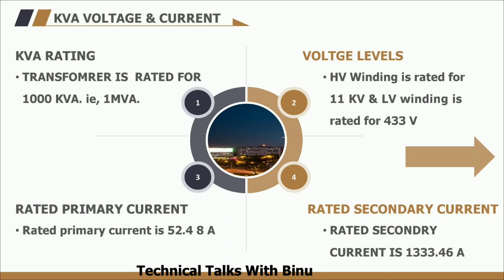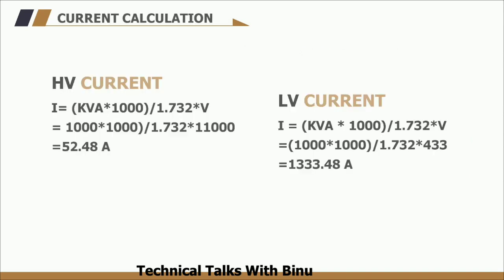Now let's see how this can be calculated. Rated current on the HT side is given by the formula: KVA × 1000 divided by (√3 × voltage). That is 1000 × 1000 divided by 1.732 × 11000, which gives 52.48 A. On the LT side, applying the same formula: 1000 × 1000 divided by √3 × 433, which gives 1333.46 A.